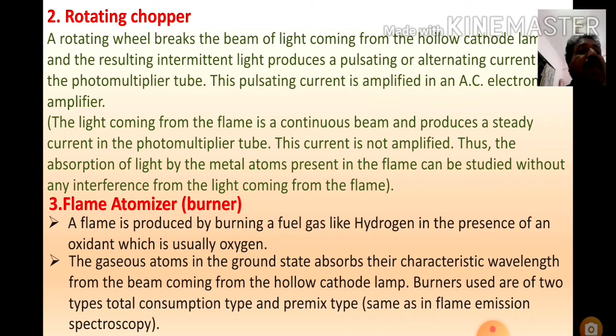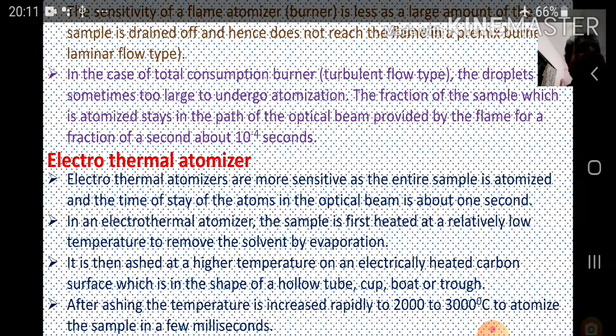The next component is the flame atomizer, that includes the burners. A flame is produced by burning a fuel gas like hydrogen in the presence of an oxidant gas, which is usually oxygen. The gaseous atoms in the ground state absorb their characteristic wavelength from the beam coming from the hollow cathode lamp. Burners used are of two types: total consumption type burner and premix or laminar flow type burner. These burners are the same as those used in flame emission spectroscopy.